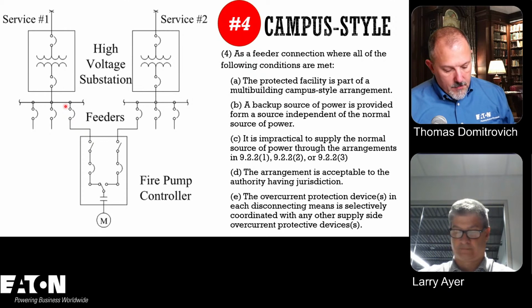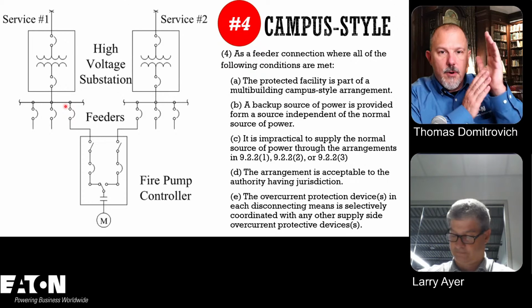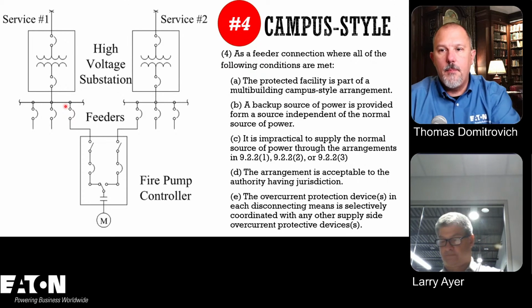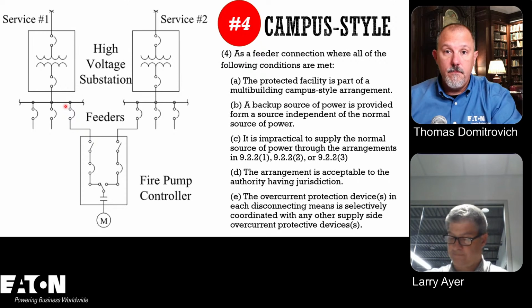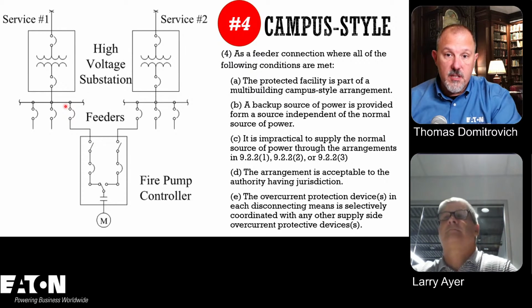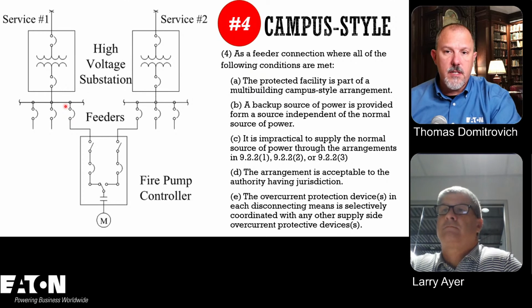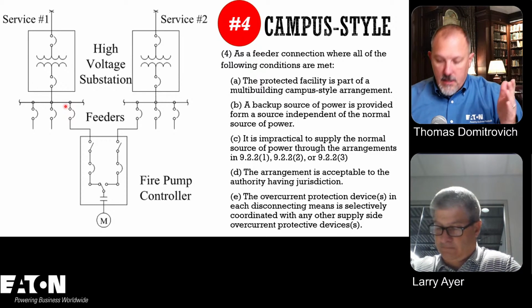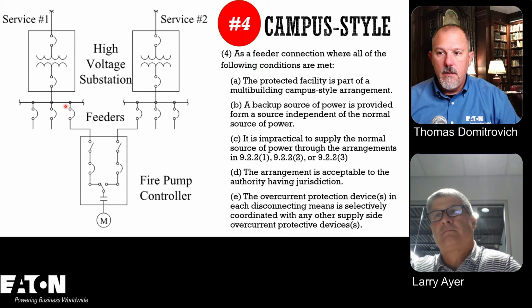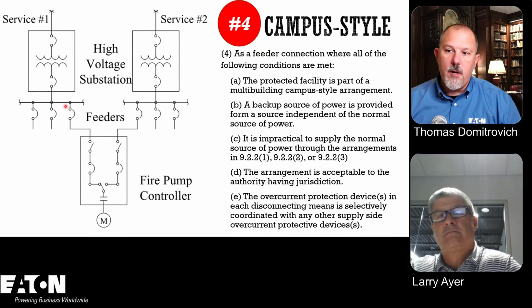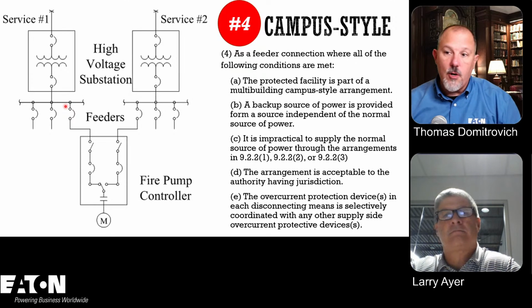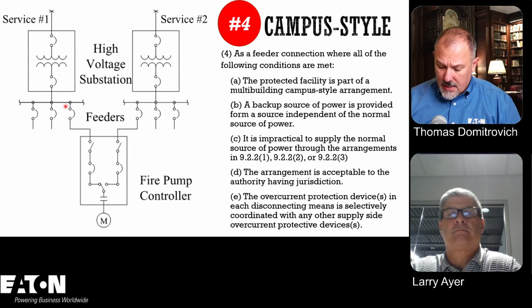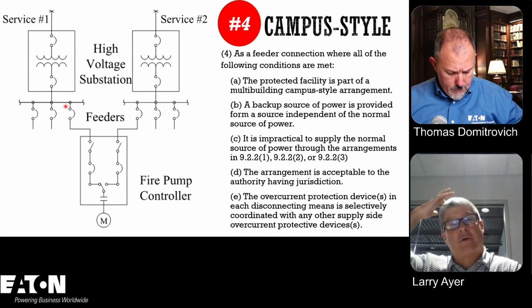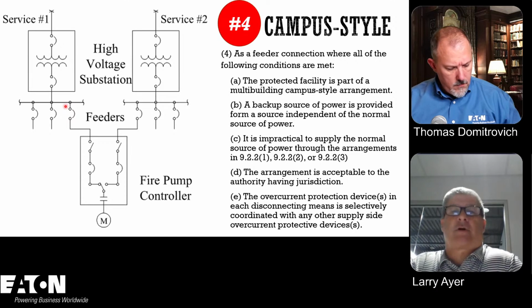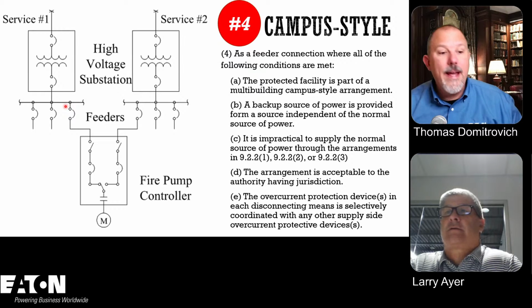Larry, correct me where you think I'm wrong, but I think you have to look at the reliability. If your primary source isn't reliable, your backup power could come from a diesel generator that's supplying power to this pump, like you would have as part of your Article 700 system. But is there a requirement in 695 that your alternate source has to be from an Article 700 system, or any special requirements on that second source? Well, let's go back to his question. Is there any special requirement for the diesel generator set if it is the only power source? Oh yeah, he did say the only power source.